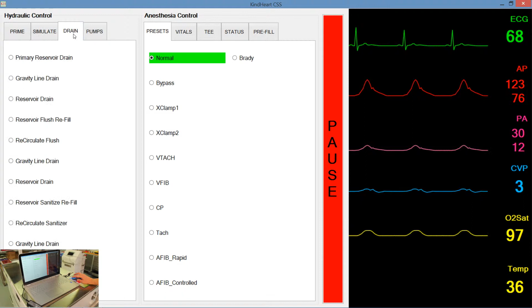hydraulic control, and the drop-down list that will occur there are to begin circulation. This is after you've primed the machine, and it will begin to circulate and pressurize the different lines in the machine. The next on the drop-down list will be de-air the lines. This will be clicked when you are de-airing the AV loop lines in order to hook up for cannulation. This activates the pumps and pressures during cannulation. And then this one starts bypass, and then the end of the simulation. This tab, the drain tab, is a drop-down list that will walk you through each of the different activities that are necessary to drain and clean the machine.